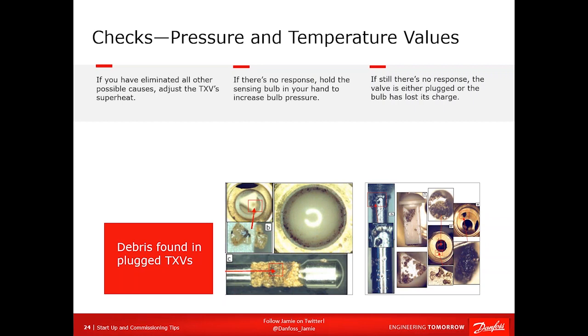All right, it's either plugged, and always look at the liquid inlet screen. Always look at the liquid inlet on a TXV to see if it's plugged or not, because now you know what happened. If that's the case, replace the filter dryer. Ask yourself why you didn't catch this crap. And number 2, flush the system, because I can guarantee you there's probably more of it in there. If you still clean, you still have to put a new TXV in, and make sure you charge according to the manufacturer's recommendation. Make sure you replace that filter dryer, and maybe, who knows, move it closer to the TXV.